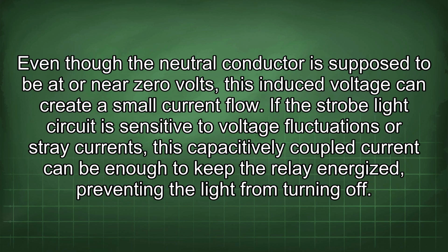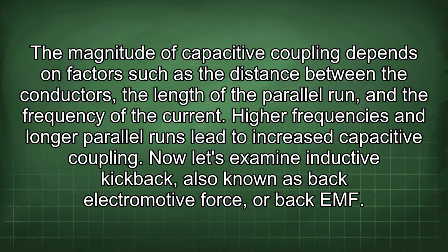If the strobe light circuit is sensitive to voltage fluctuations or stray currents, this capacitively coupled current can be enough to keep the relay energized, preventing the light from turning off. The magnitude of capacitive coupling depends on factors such as the distance between the conductors, the length of the parallel run, and the frequency of the current. Higher frequencies and longer parallel runs lead to increased capacitive coupling.